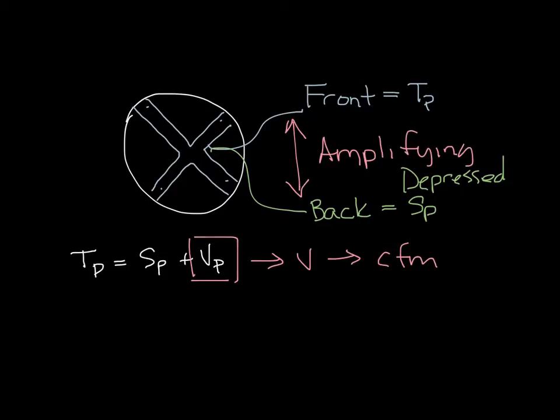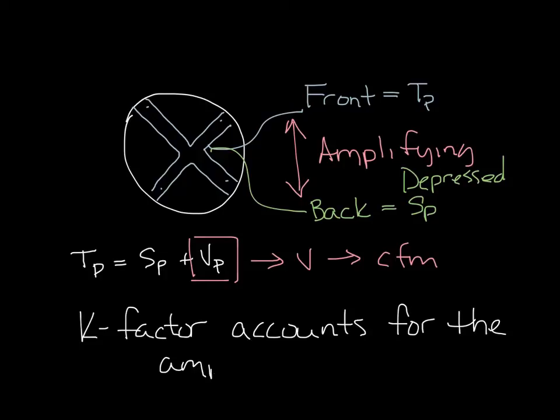The K-factor is the constant for each sensor size that corrects for the amplification so that the controller can calculate CFM from this amplified signal.